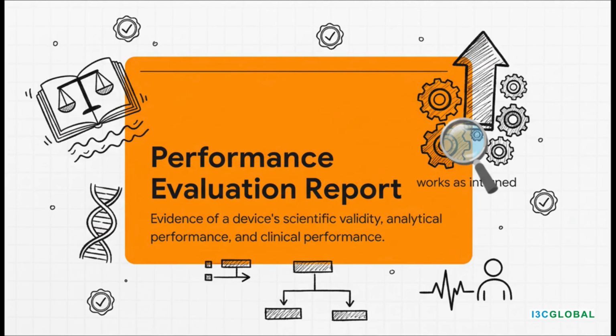Yeah, let's zoom in on that performance evaluation report, the PER, for a second. This is not just some other piece of paper. You've got to think of this as the absolute cornerstone of your entire submission. It's where you pull together all the evidence, and I mean all of it, that proves your device does exactly what you say it does. It has to cover scientific validity, analytical performance, and clinical performance with hard data to back up every single claim.